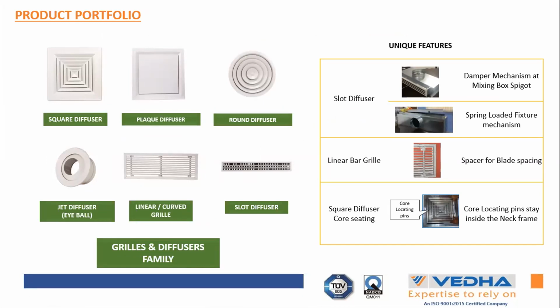Each product has a unique feature, exclusive to that product only. You can see that even the slot diffuser has a spring-loaded fixing mechanism and a damper mechanism inside the spigot. For the grills, we have spacers for the blade spacing. And for the square diffuser, we have core locating pins and a spring-loaded mechanism. So each of our products has very different features, very unique to our product.